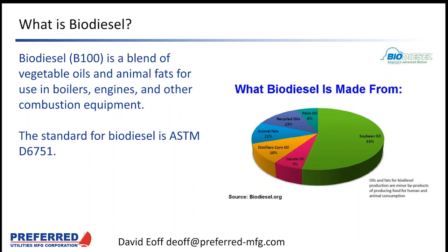So, like a James Michener novel, we're going to start at the very beginning and explain what biodiesel is. Biodiesel is basically a blend of non-fossil fuel, vegetable oils, and animal fats for use in boilers, engines, and other combustion equipment. The standard for biodiesel is ASTM D6751. The exact blend will vary by batch, but the final result must meet ASTM D6751. And if you can't read that graphic on the screen, it says that biodiesel is typically made from 53% soybean oil, 7% canola oil, 10% distiller's corn oil, 11% animal fats, 13% recycled oils like recycled cooking oil, and 6% palm oil. But this can vary from batch to batch within the specification.